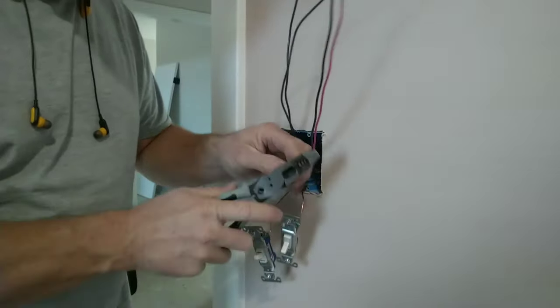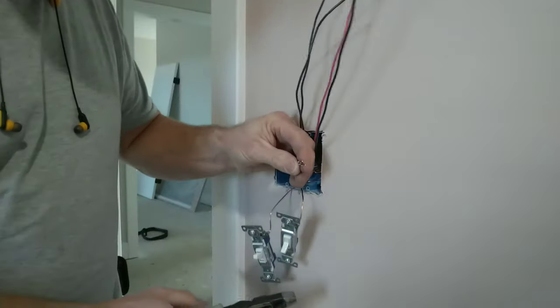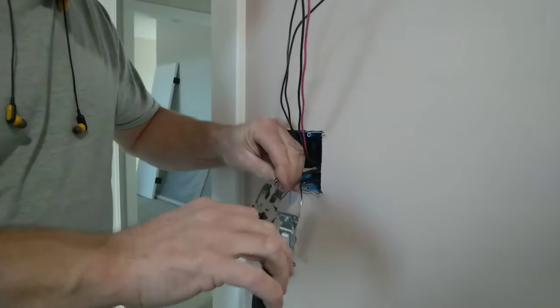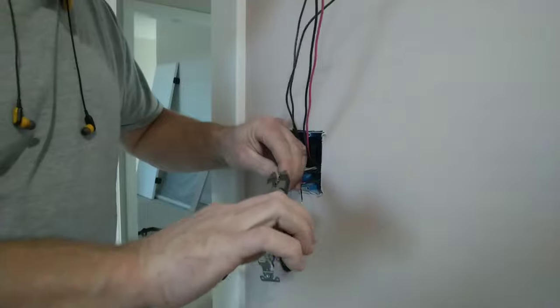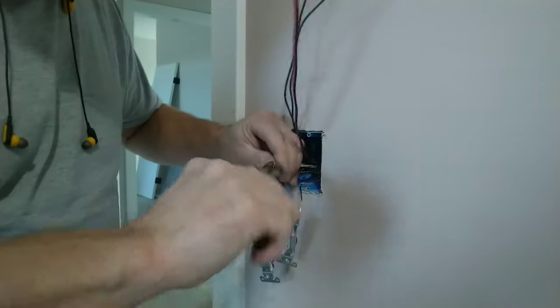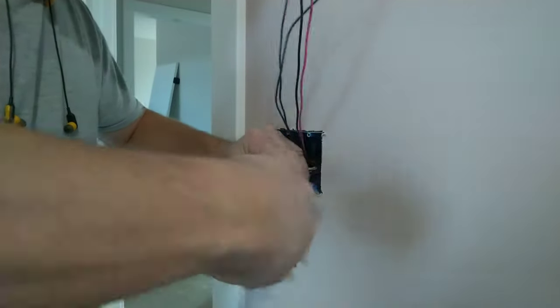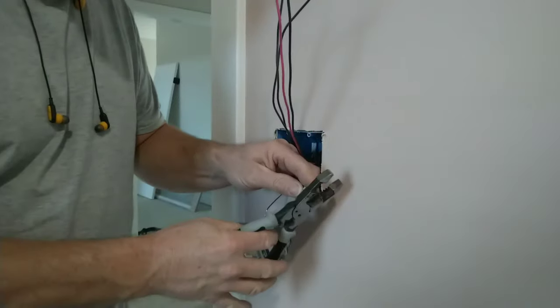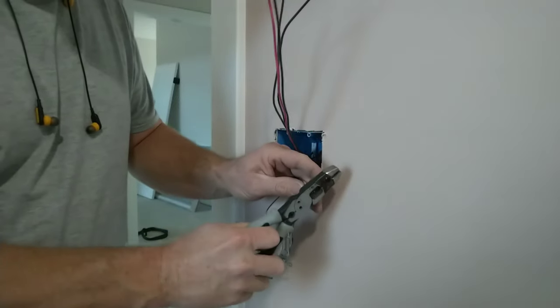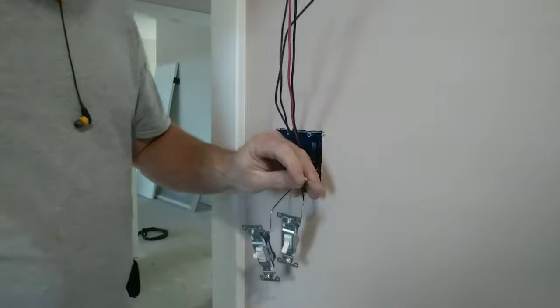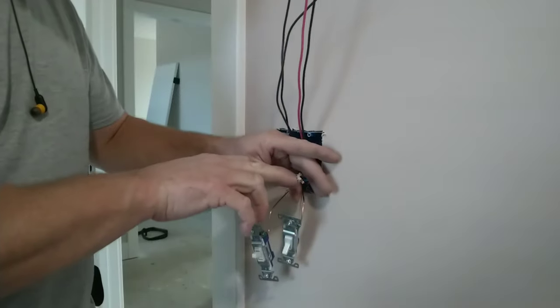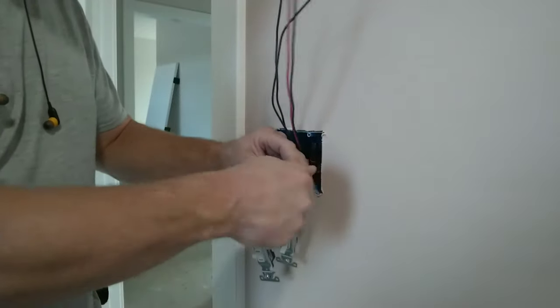Now what I'm gonna do, because we've been moving these wires around, I'm gonna flush them up. Now if you don't wanna stab your fingers, you can put your cutters to them and then grasp tightly. Grab all three of your wires and loose grip, put these on, loose grip, and let this spin over the wires. And you're gonna see about 7/8 of an inch out. I'm gonna cut it back so that I've got about 5/8 of an inch now. We're gonna take on 14 gauge wires. We're gonna put a yellow wire nut on it.